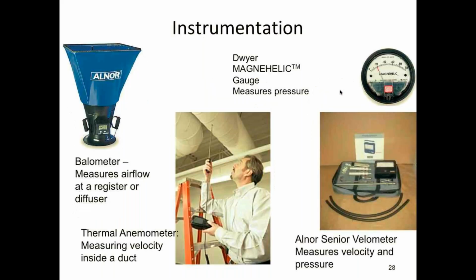You have to be tested right there in the strip. I'm sorry? You have to have it close to the strip of the thing. I'm not sure I understand. Oh, because I think you were saying for her to move a little bit closer. Oh, only because I wanted to get a measurement. Oh. Okay, at that point she was 3 inches away, right? She measured 250. The minute she went to 6 inches away, it dropped down to 50. So the impact of distance on this is enormous. And the way we get around that is by building the hood so that it doesn't pull air in from places you really don't need it. It directs the area that you're going to pull air in from.